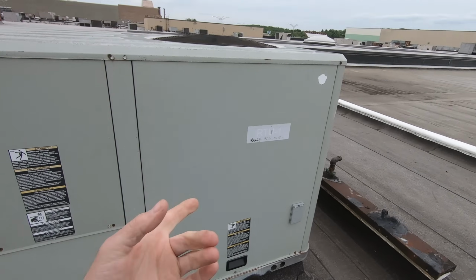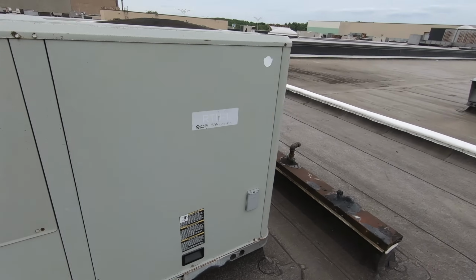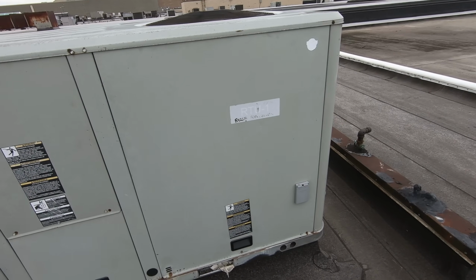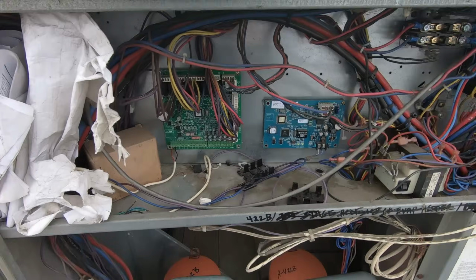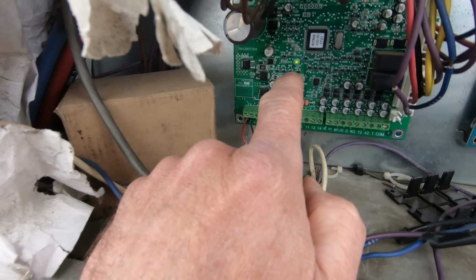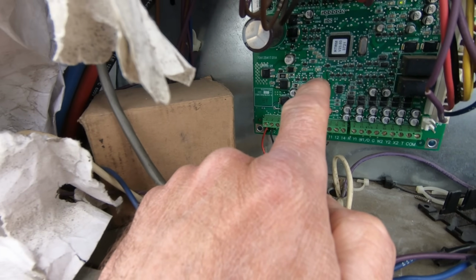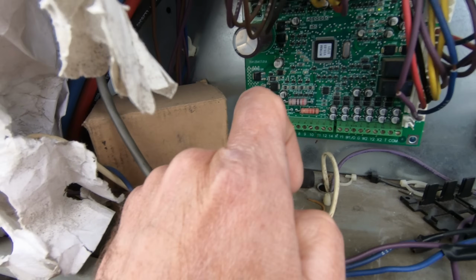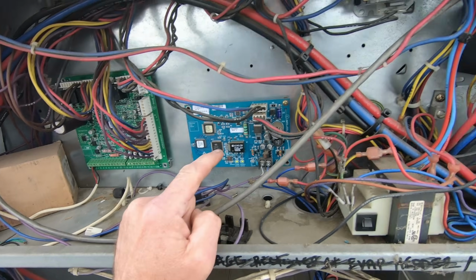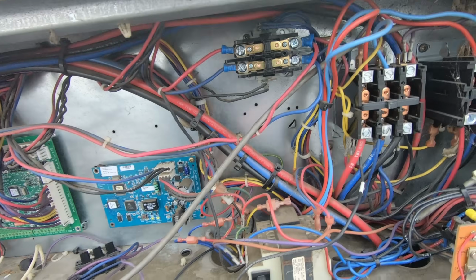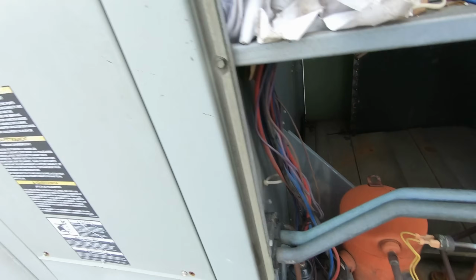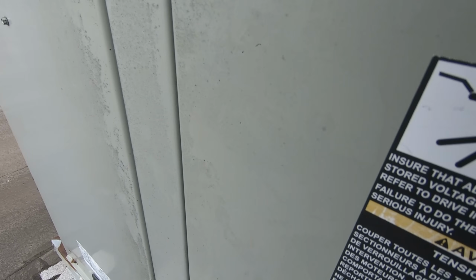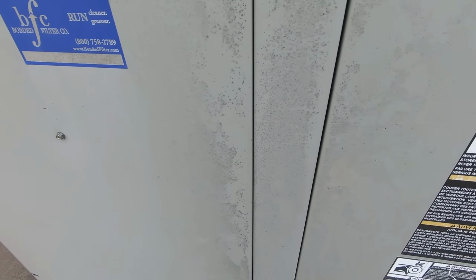I'm gonna open up the electrical/compressor compartment and see what we've got going on there. All right, well, we have power. I haven't checked it with a meter, but I see 1, 2, I see lights flashing. This is our EMS control board. Our blower contactor is pulled shut. I do hear something, but I think we have no belt.